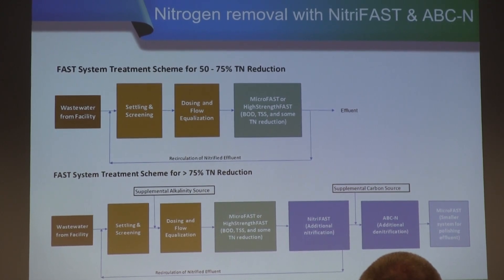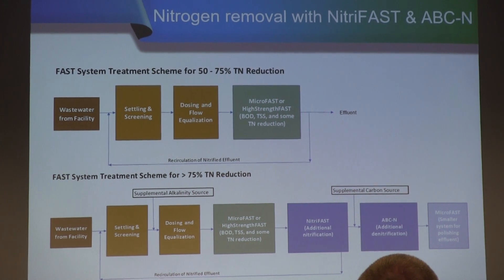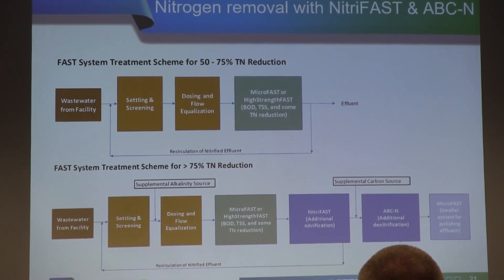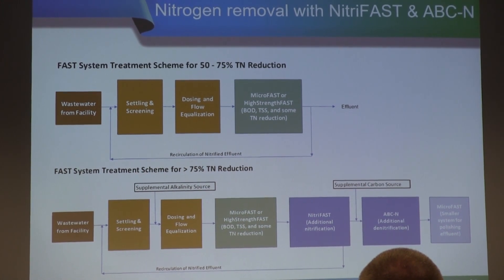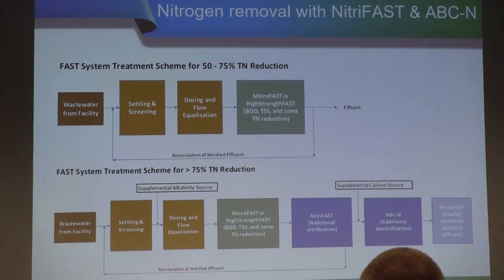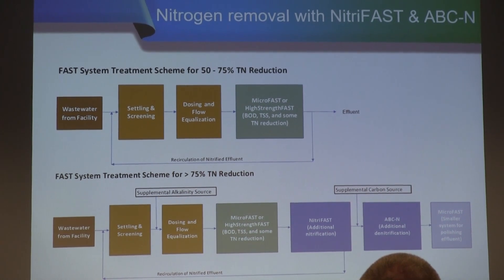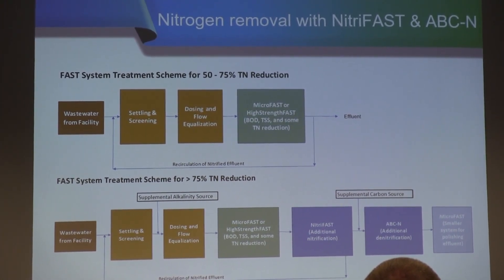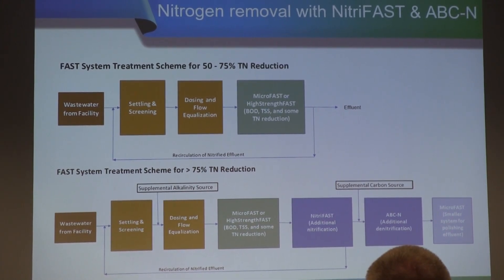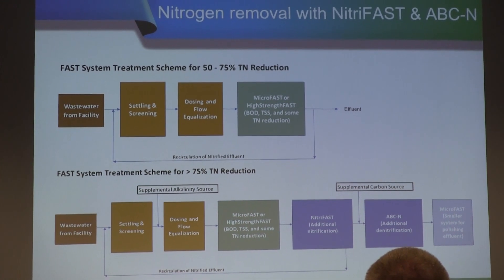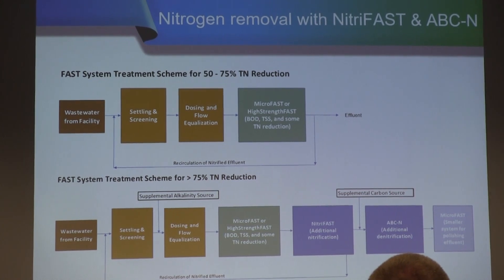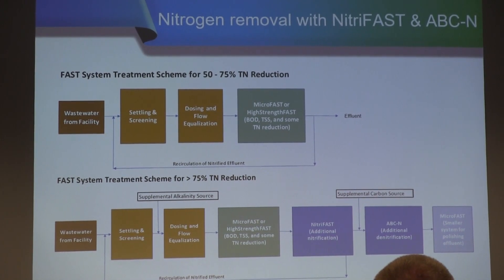Here's a brief example comparing two treatment schemes. The top flowchart shows a commercial facility where wastewater goes through a settling and screening tank for bulk solids removal, followed by dosing and flow equalization, then a secondary treatment unit. This setup is typically good for 50 to 75 percent total nitrogen removal. We sometimes suggest recirculating a portion of treated water at the outlet back to the inlet, which also helps some with total nitrogen reduction.